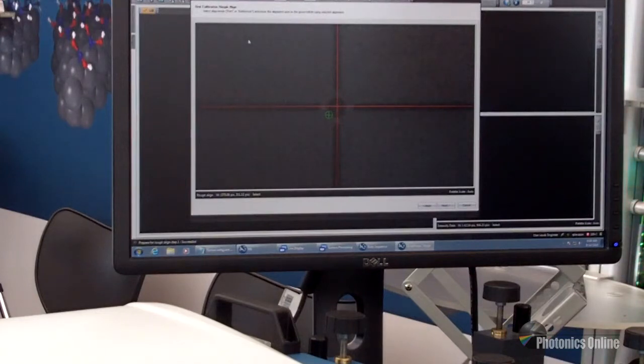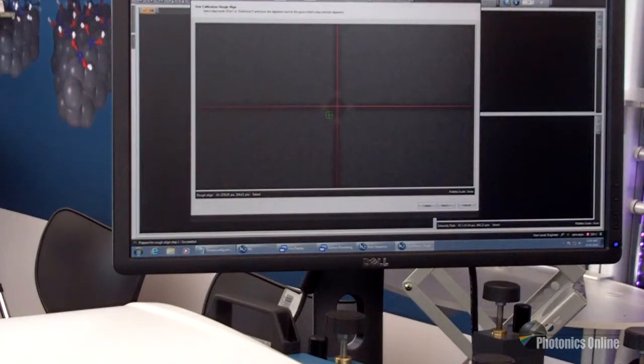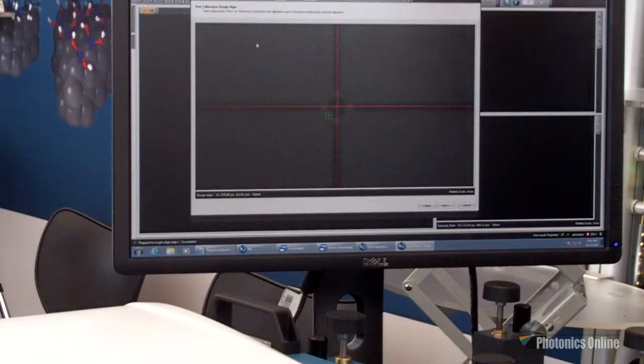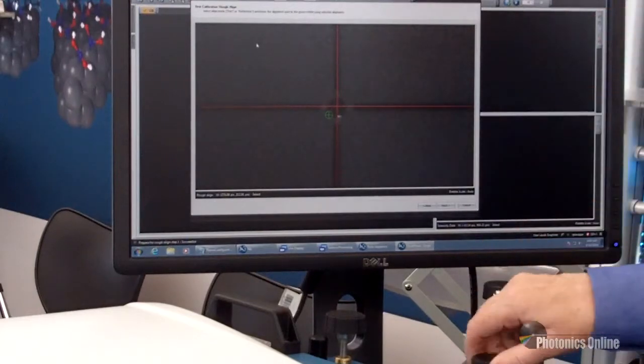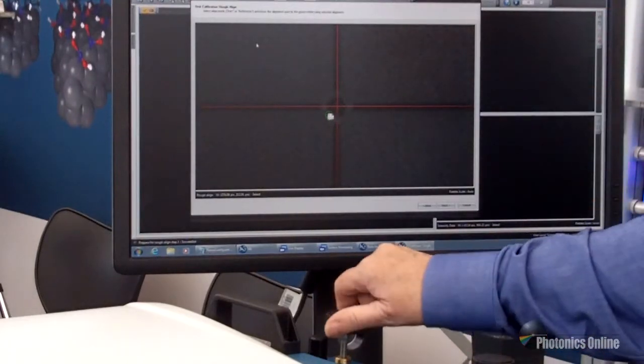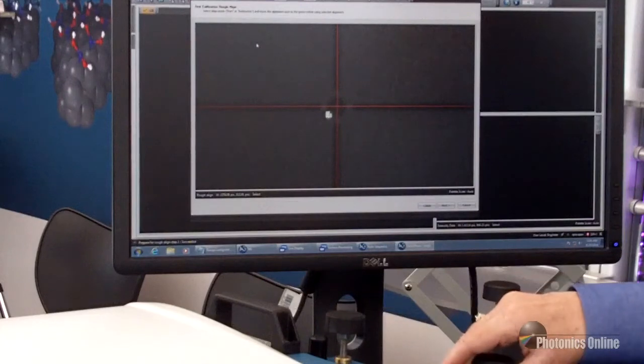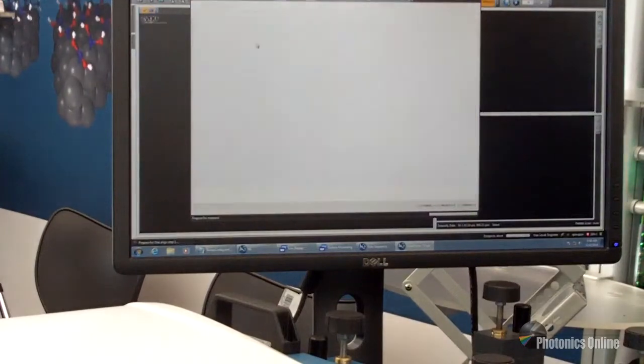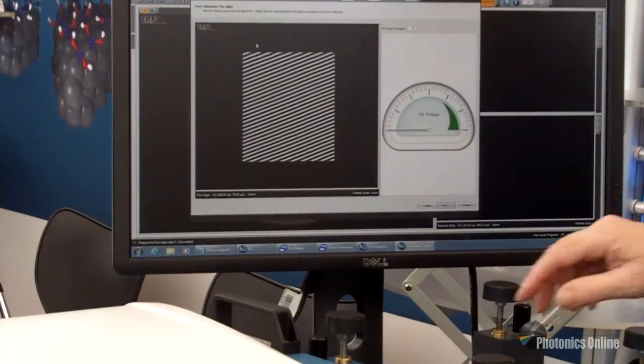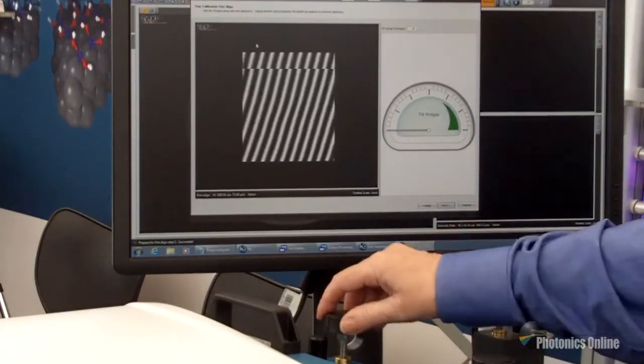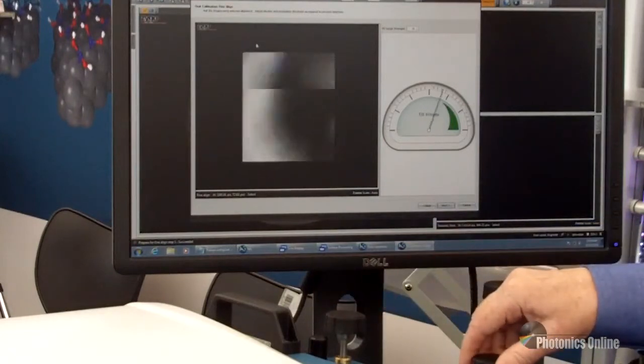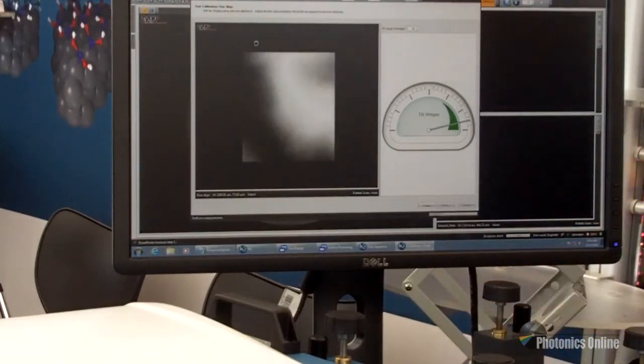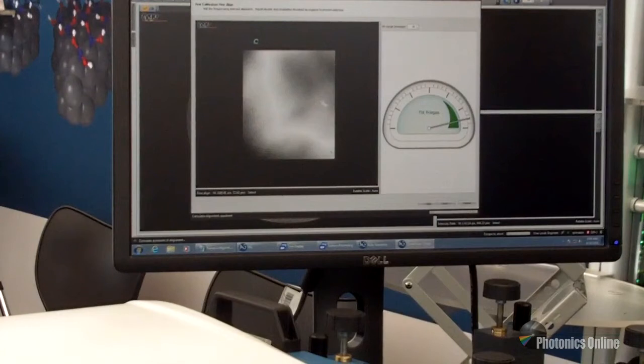And then we have the choice of introducing tilt with a target for this calibration mode. I can introduce, in this case, the tilt of the part or tilt of the reference, the reference being the master optic. Again, this is one step in a calibration mode, wizard-based, to allow me to optimize the ideal amount of tilt being introduced.